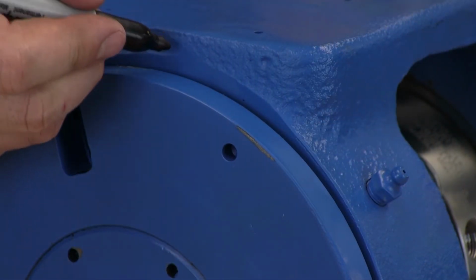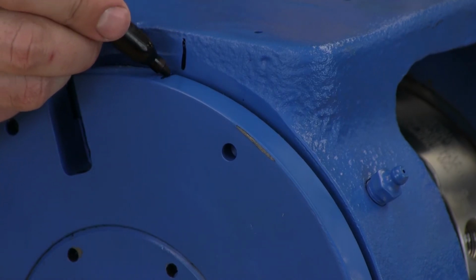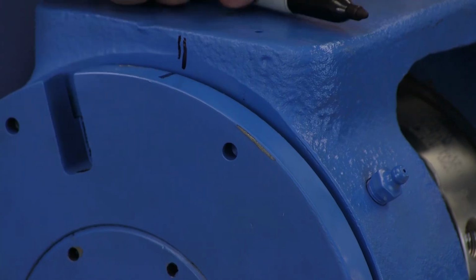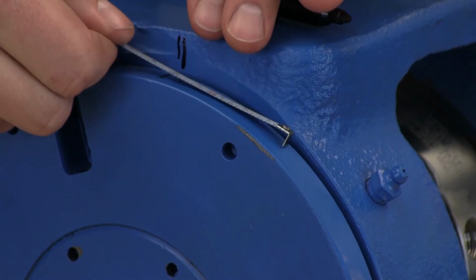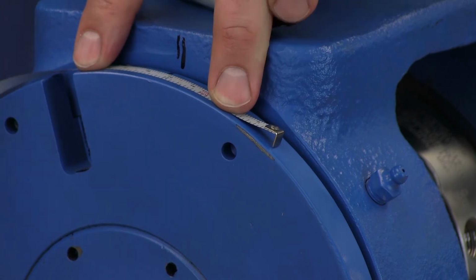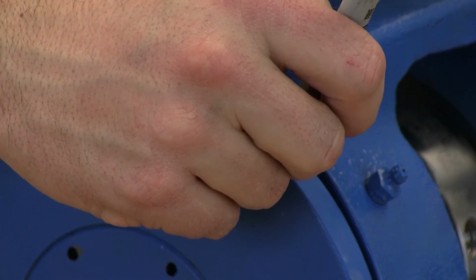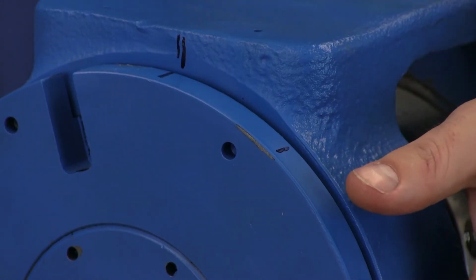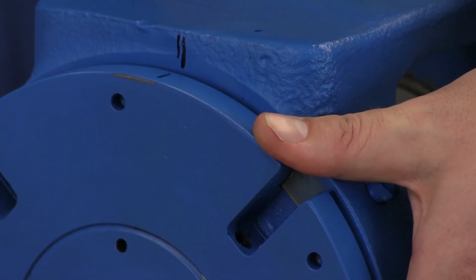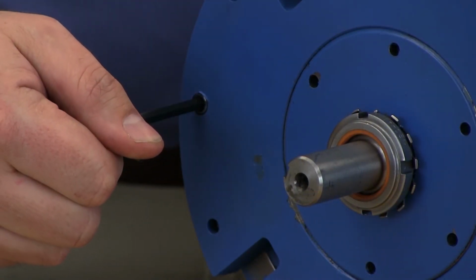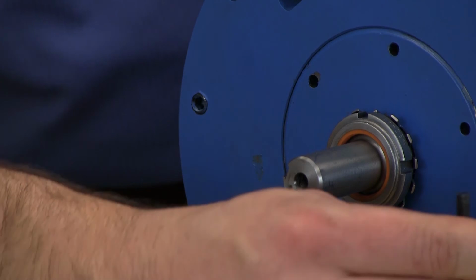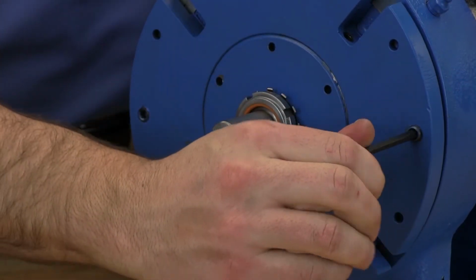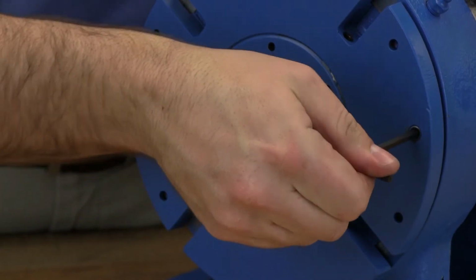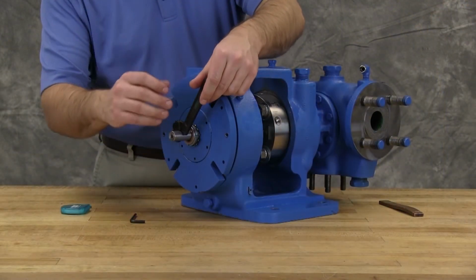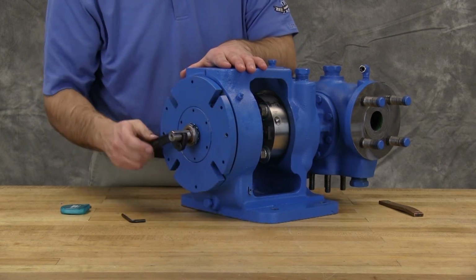Mark the position of the bearing housing with respect to the bracket. Using the measurement from the table in the technical service manual, make a second mark to the right of the first mark on the bearing housing at the specified distance. Tighten the two self-locking set screws in the outboard face of the bearing housing with equal force against the bracket. The pump end clearance is now set and locked. Be sure the shaft can rotate freely. If not, back off an additional length on the outside diameter and check again.